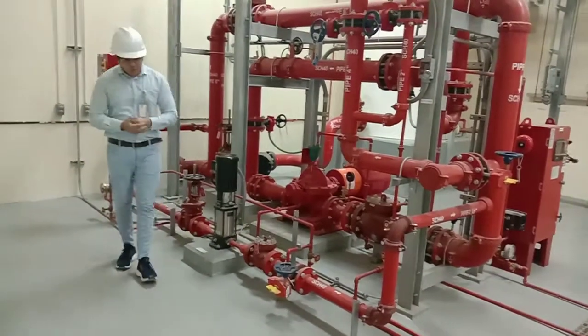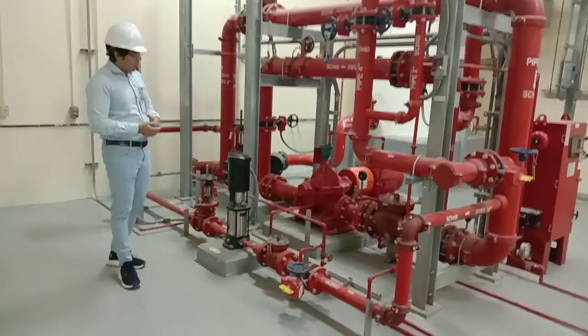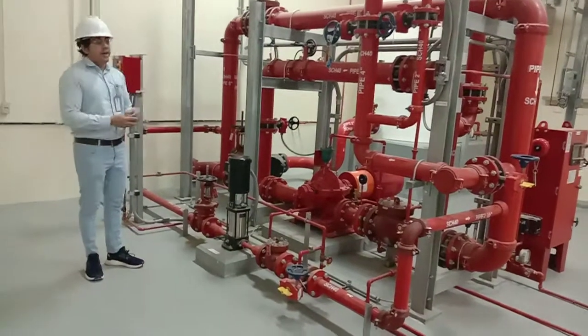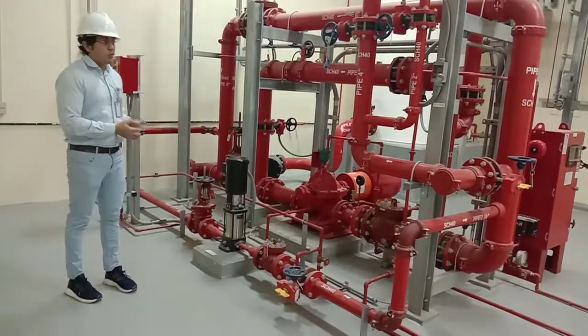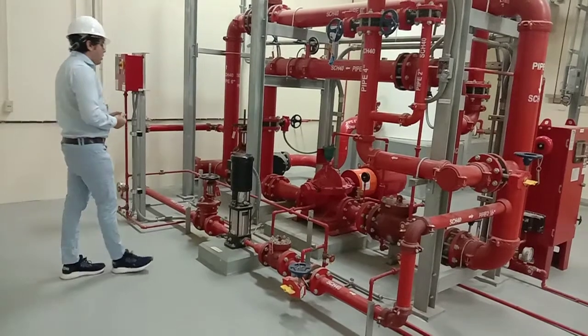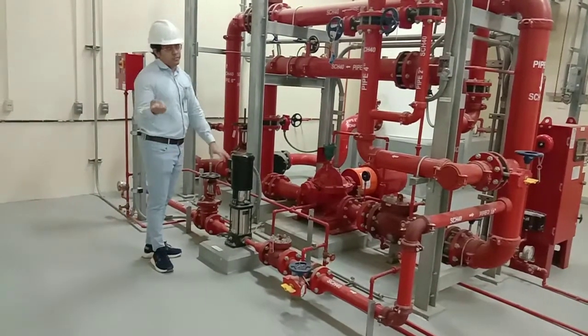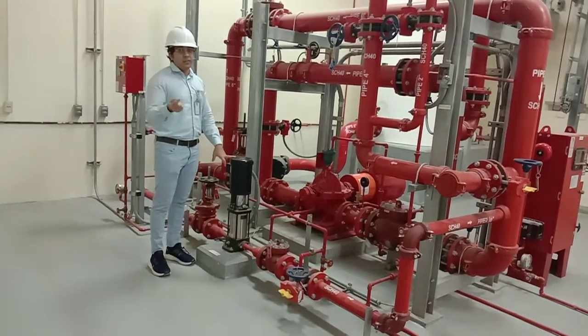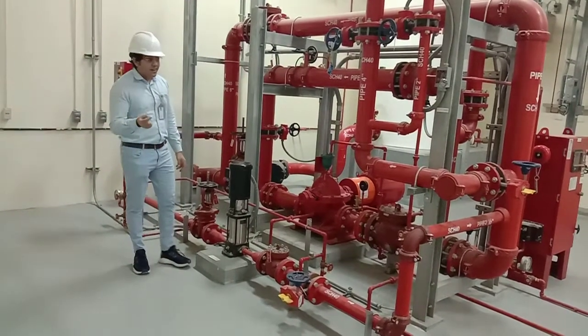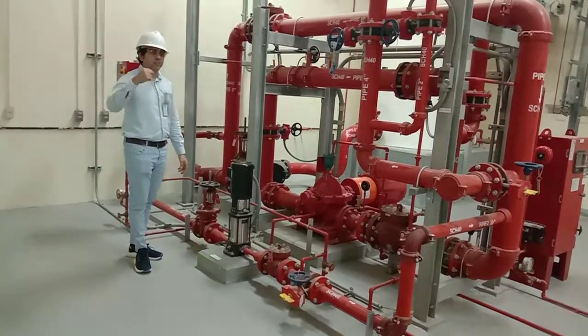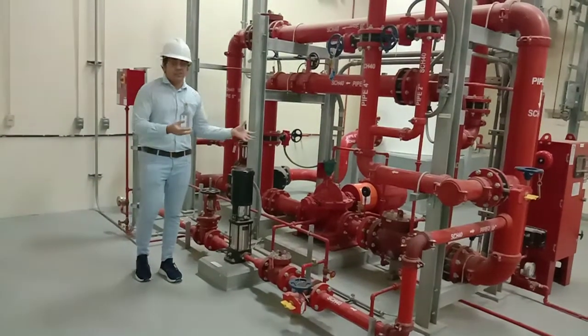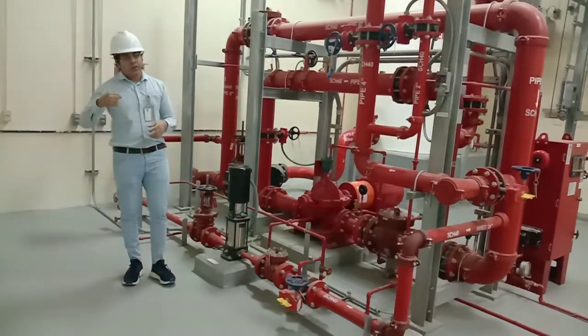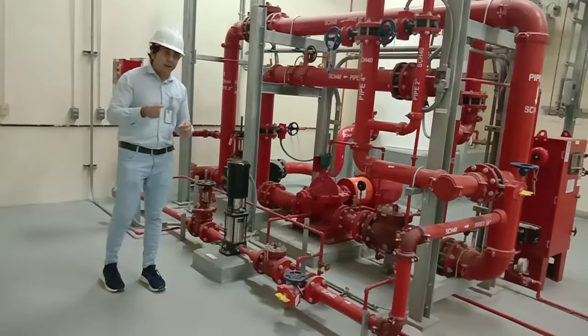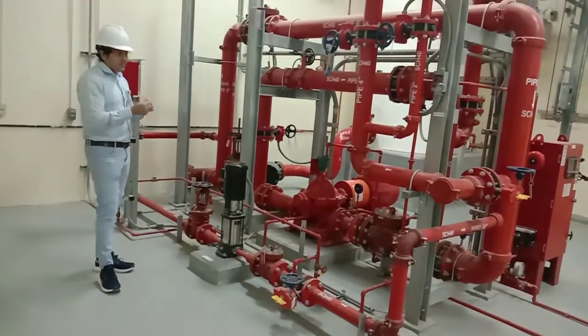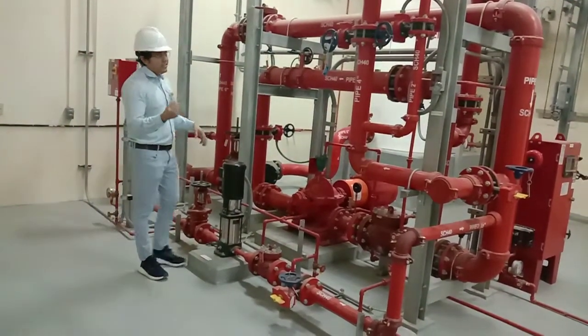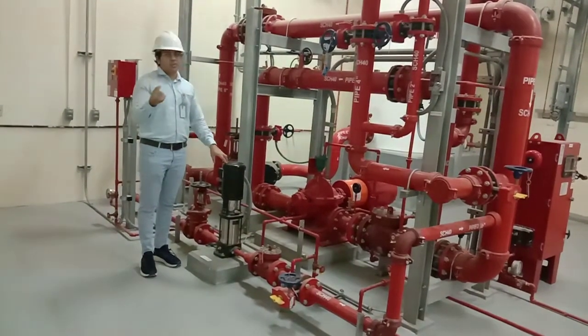We're moving on to the jockey pump, or let's say maintenance pump. You only require a maintenance pump or jockey pump to maintain the pressure in the fire protection system. What is the meaning of maintaining the pressure inside the system? It means that if your fire protection system gets a small leakage, which is very obvious in underground fire water networks, or at the bends, at the joints, in the threaded connections, gaskets, in all those areas, there might be some kind of leakage, right? So that leakage, a very small one.